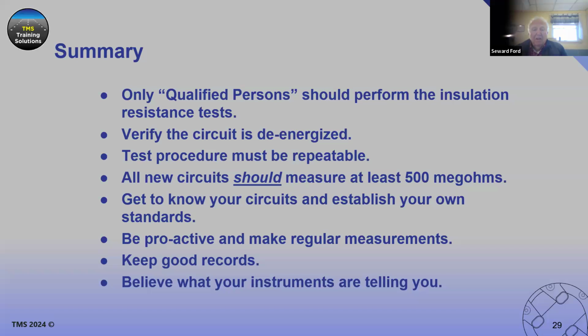Depends on the years. Well, here's a little bit of a summary here: only qualified persons should perform the insulation resistance test. You got to know what you're doing. You got to verify the circuit is de-energized. The test procedure you use must be repeatable. However often you do it, you want to make sure you do it the same way every time. And all circuits should measure at least 500 megohms. That's kind of a rule we put in there.